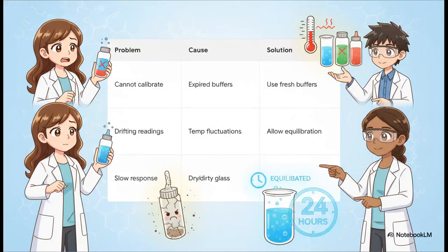Before we finish up, I want to leave you with this high-yield troubleshooting guide. If you find you just cannot calibrate, check your buffers. They might be expired or contaminated. If you're seeing drifting readings, it's almost certainly temperature fluctuations altering the glass impedance, so you need to let the system thermally equilibrate. And if your electrode has a painfully slow response, the glass is probably dried out. Just submerge it in the proper electrolyte to rehydrate for a full 24 hours. Empower yourself with these solutions. I promise, they'll save your research.